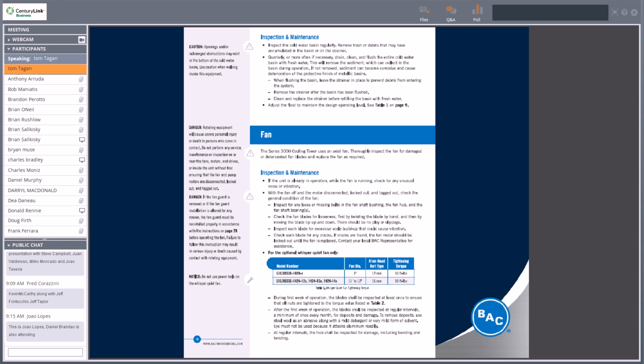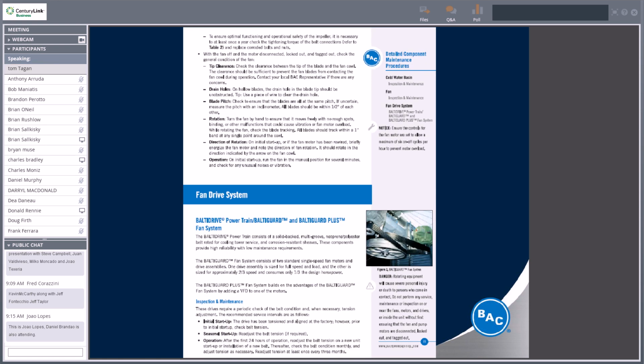Again, checking for cracks. A lot of the preventive maintenance of cooling towers starts with the look and listen philosophy. It always recommends after starting this up, whether it's a new installation or starting it up again for the first time, to readdress the fan belt tension if you're using a belt, or verifying that your gear and the gear drive assembly is still in alignment.